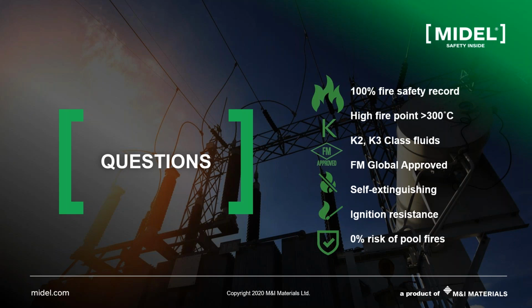Because esters allow running hotter without degrading the paper. They will not increase the fire risk. But based on other retrofilled 11 kV transformers, we wouldn't expect more than a 2 degree increase in top liquid temperature. Okay, and whether it's retrofilled or new, it'll be the same performance. Yes, whether retrofilled or new, if you compare mineral oil to an ester for 11 kV, I expect a 2 degree higher top oil temperature. For the winding temperature, the average copper winding temperature can also be 2 or 3 degrees higher. Yes, and this all depends on how hot the transformer is operating and the ambient temperature.